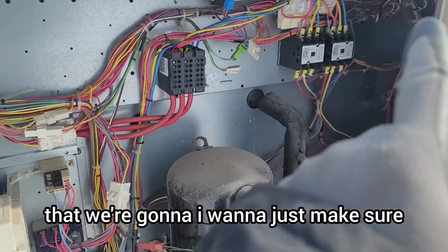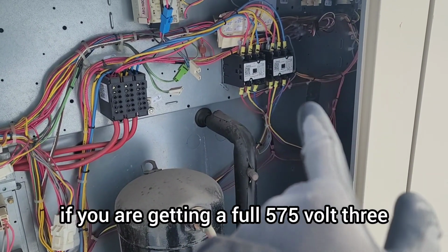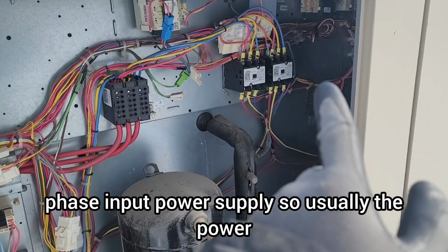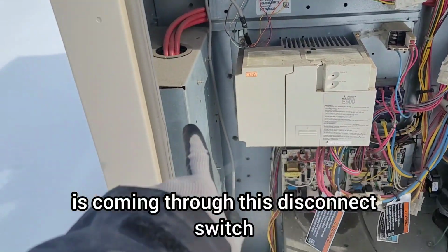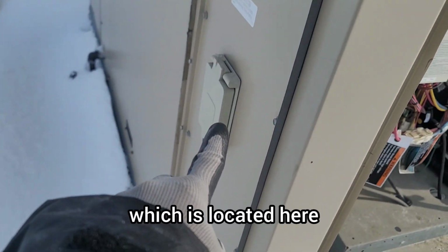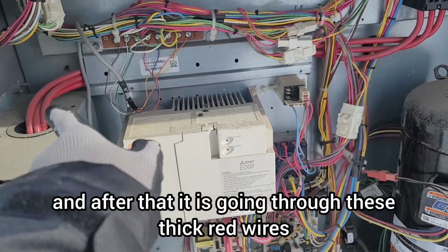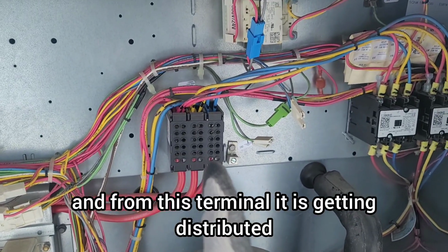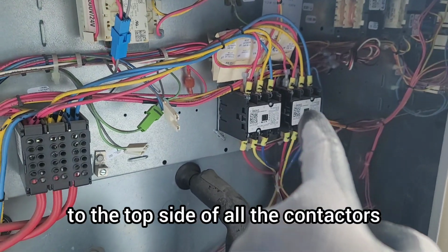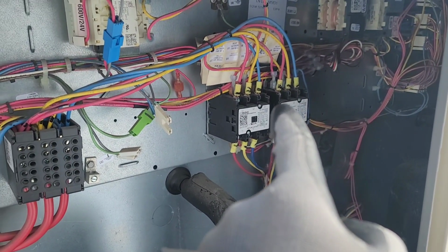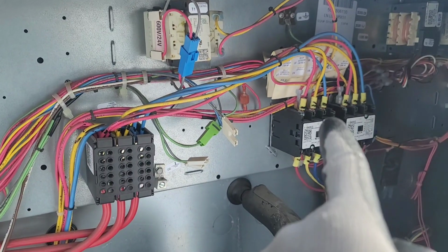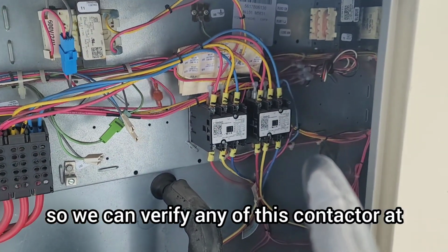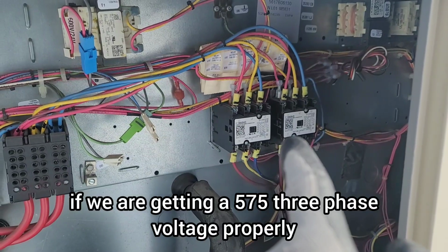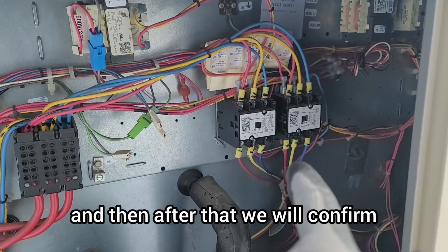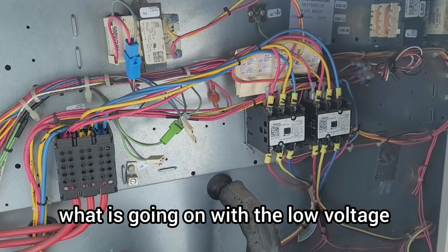And before doing that, I wanna just make sure we are getting a full 575 volt three-phase input power supply. So usually the power is coming through this disconnect switch, which is located here, and after that it is going through these thick red wires to this terminal, and from this terminal it is getting distributed to the top side of all the contactors. On the top side they are connected in parallel, so we can verify any of these contactors at the top portion if we are getting 575 three-phase voltage properly, and then after that we are going to confirm what is going on with the low voltage.